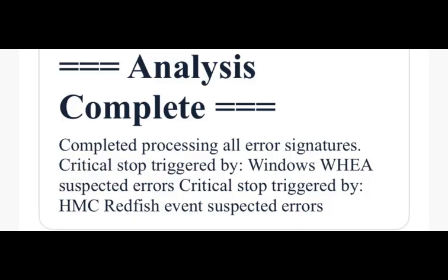That's exactly what it was. They had an issue with a specific device on the power delivery board inside the node. The failure rate was super low, maybe fractions of a percent. It only seemed to fail under very specific transient high-power conditions that would only pop up occasionally during the really intense volume validation tests. But when it failed, the node wouldn't boot. Dead in the water. Huge impact. But trying to reproduce that specific spike condition on a specific node in the lab, good luck. There's too much variability across the components, even within the same batch.